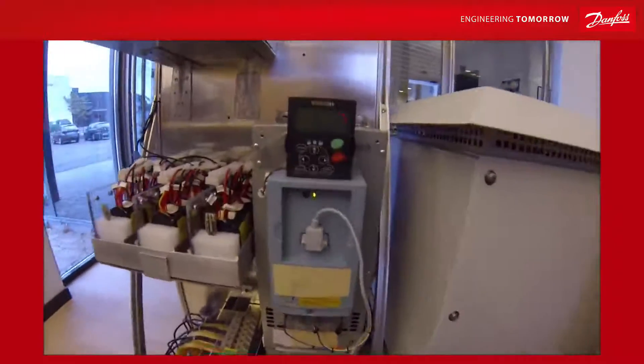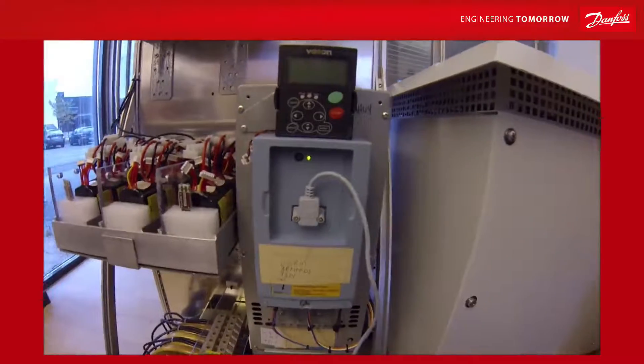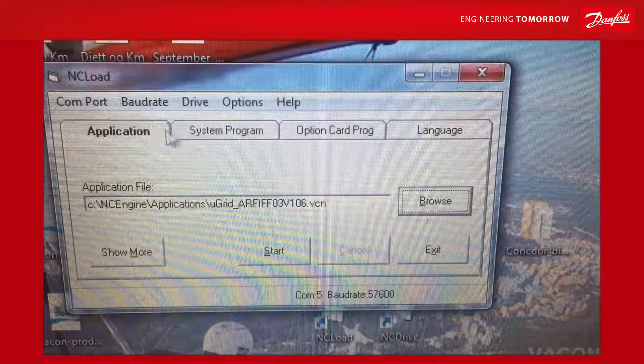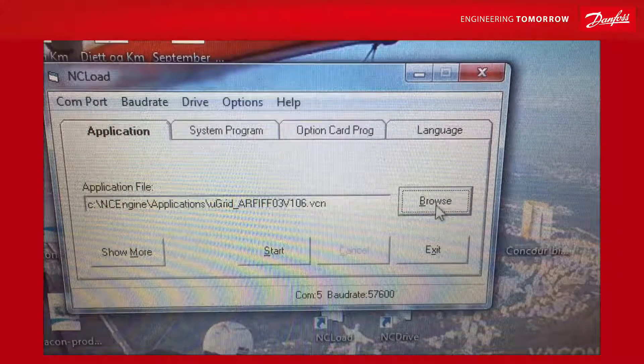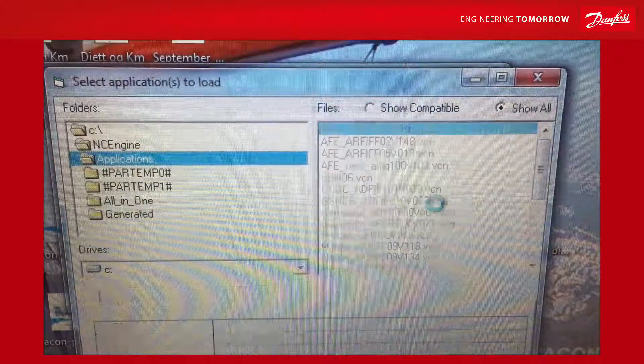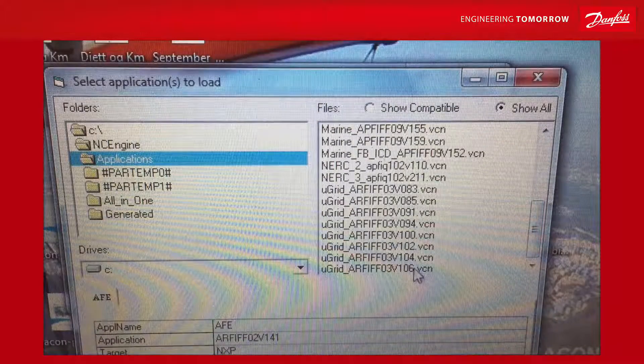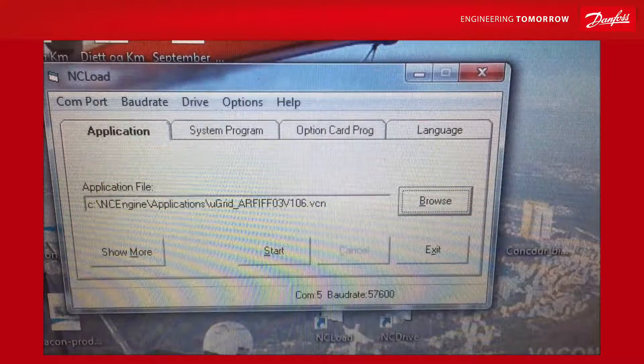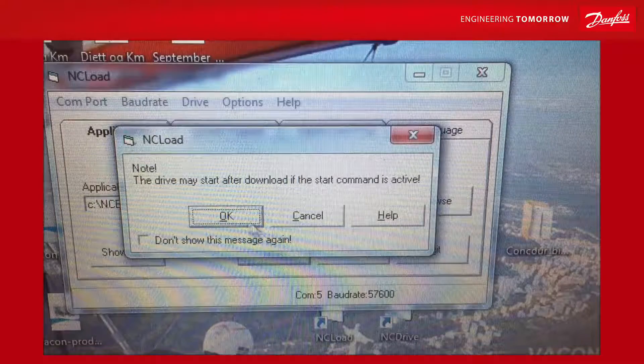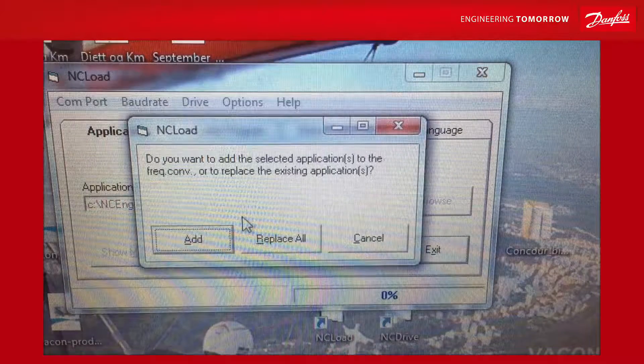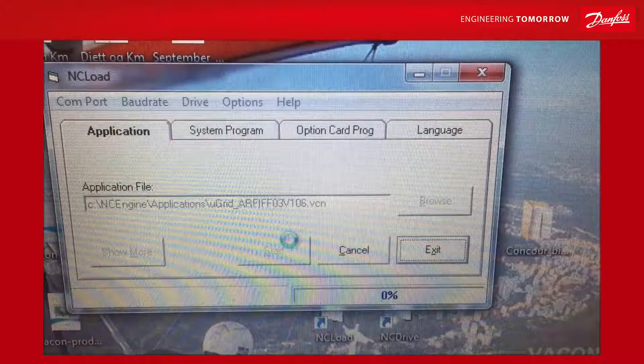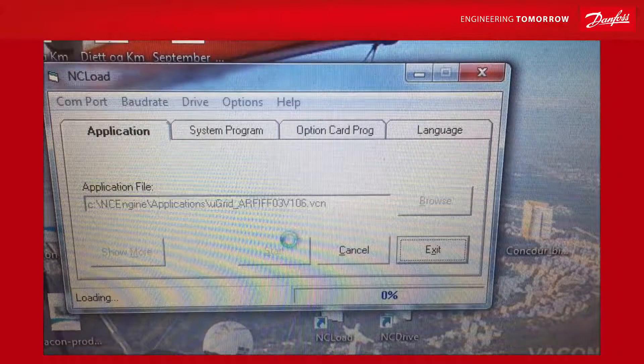The frequency converter is a regular frequency converter straight out of the box. To make it into a grid converter we have to download the software for the grid application. On my laptop computer I have stored this VCN file. Under the application I have stored I will find the latest version, which is version 106. I will select 'replace all', which means everything application-wise will be overwritten with this application.